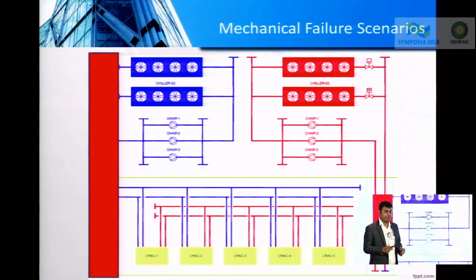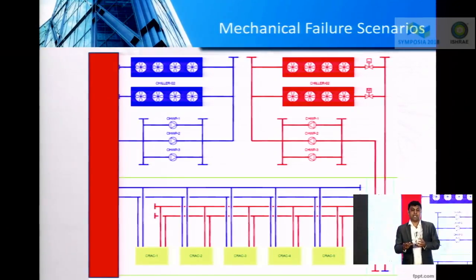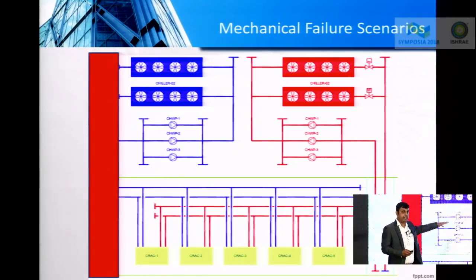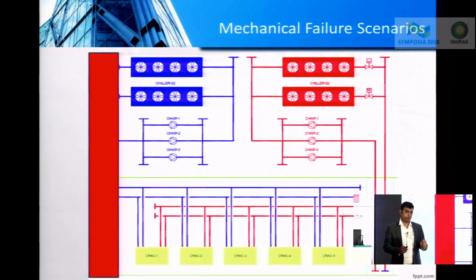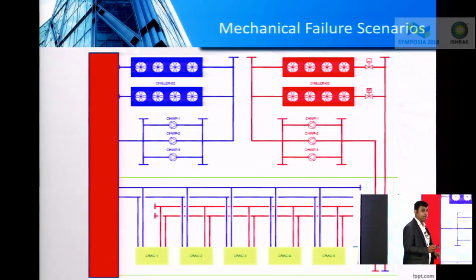Nowadays, it's very common to go with buffer tanks, which means if your cooling fails completely, your buffer tanks can help you sustain for at least 4 to 5 minutes, depending on the size of your buffer tanks. So I can also simulate the complete failure of cooling and see how the buffer tank behaves at full load condition. So these are some of the failure points that you can simulate during mechanical failure scenarios.